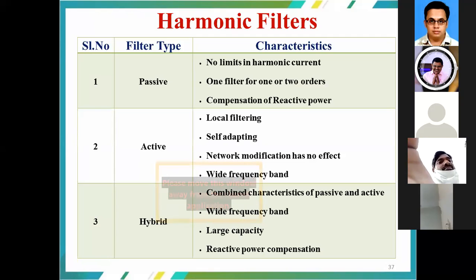And the next one is the elimination of the harmonics. The first one is the harmonic filters. In the harmonic filters, we have the active type, passive type, and the hybrid type. In the passive type, there is no limit on the harmonic current. We can design it for any rating, one filter for one or two orders, but it is frequency dependent, and compensation of reactive power is required. In the active harmonic filters, we have local filtering, and it is self-adaptable. Network modification has no effect, and it has a wide frequency band. Hybrid means a combination of the advantages of both active as well as passive.